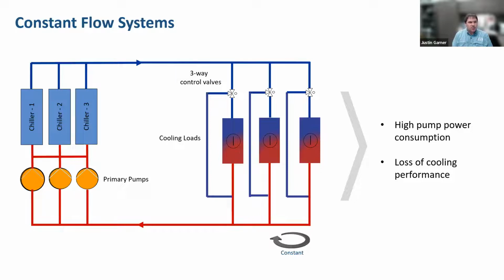So obviously, as your load decreased out at your air handling units or fan coils or whatever they may be, your delta T would decrease on your chillers because you weren't really modulating your chiller loading and you weren't modulating your pumps and your flow. Go ahead and go to the next one, Pete.